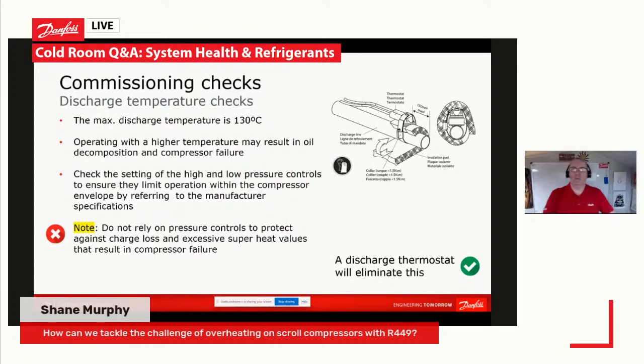So there we go. So commissioning checks, discharge temperature. Yeah, the easiest way, Shane, is to fit a discharge gas thermostat on the discharge of the machine. And that will cut out basically at 130 degrees C, and then cut back in, I think it's 15 degrees lower than that from memory. But yeah, that's the easiest way to monitor our discharge gas temperature.